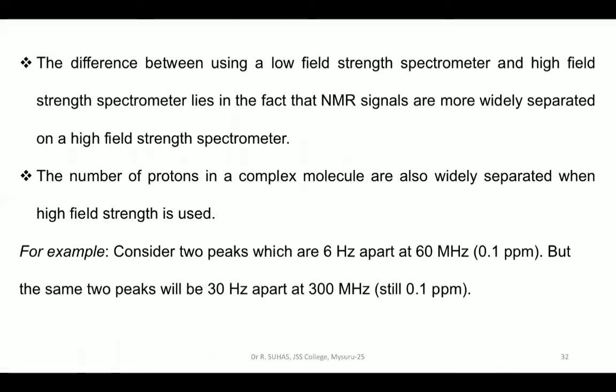So what is the difference between using low-field and high-field strength spectrometers? It is mainly for zooming purposes. NMR signals are widely separated on a high-field strength spectrometer. For example, two peaks 6 Hz apart on a 60 MHz instrument is only 0.1 PPM, but the same two peaks will be 30 Hz apart on a 300 MHz instrument — yet the chemical shift value remains 0.1 PPM. The separation of peaks is much greater with high field strength, making it easier to elucidate the structure of complex molecules.